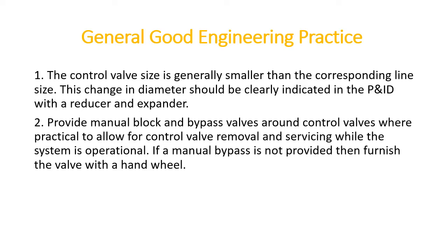But in some cases the bypass is not possible, like in very critical service, or where there is a chance of choking or slurry material is being used. In some specific cases the bypass is not provided because of process constraints. In that case there should be a handwheel. The valve should be equipped with a handwheel so that if the valve gets stuck, it can be opened or closed using the handwheel.